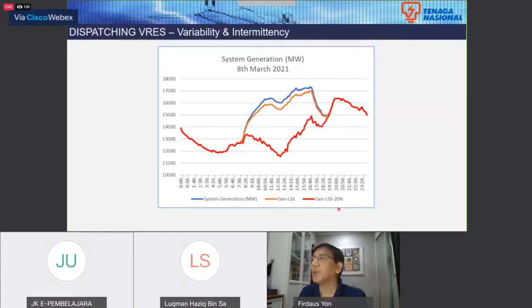But if we go up to 20%, meaning solar is 20% of generating capacity, I did a simple analysis with a few assumptions. With 20% solar, this is what the generation without solar would be - the blue curve is generation with solar, the red curve is generation without solar if solar is 20%. Can you see the gap? This is the biggest gap at this point - the gap is about 11,500, and the required demand is 16,000.